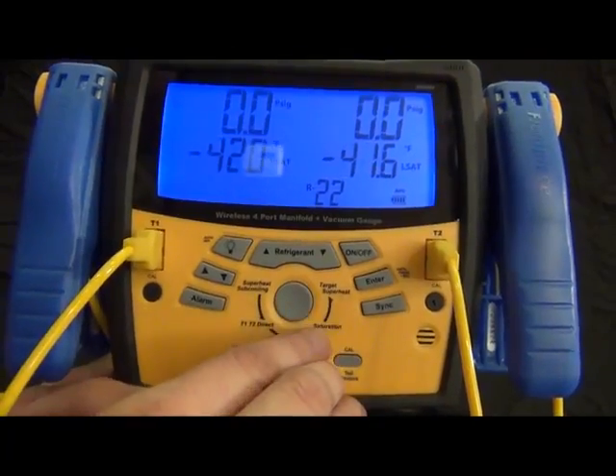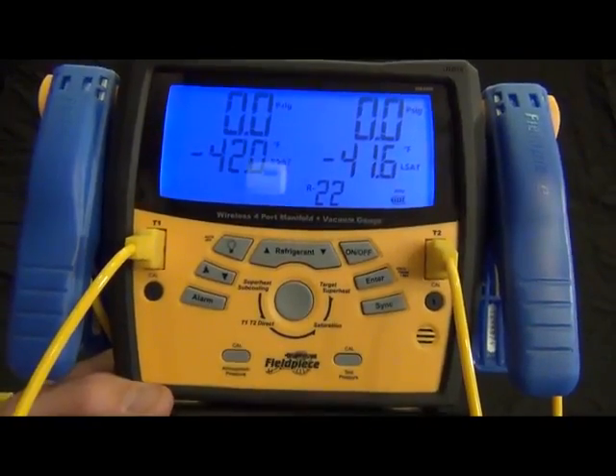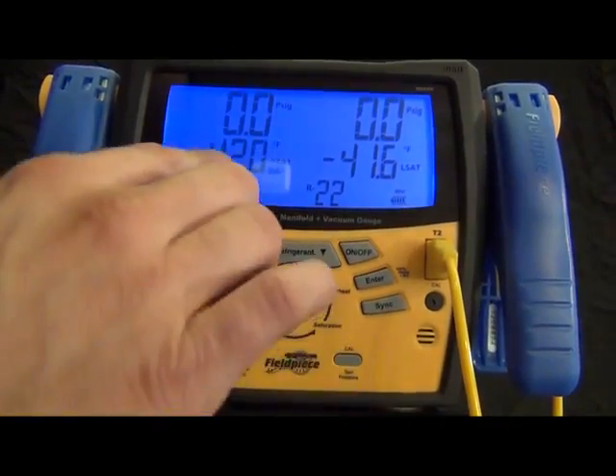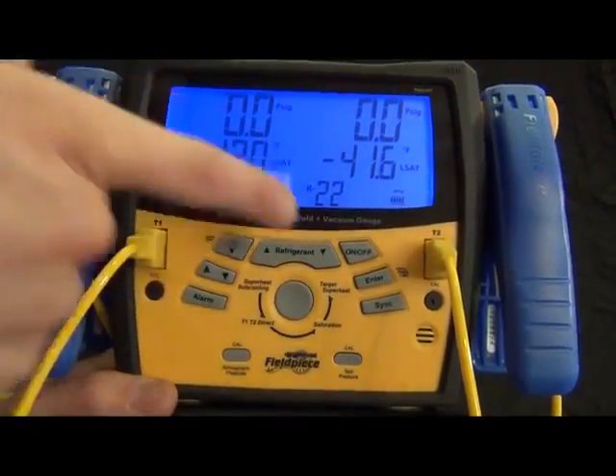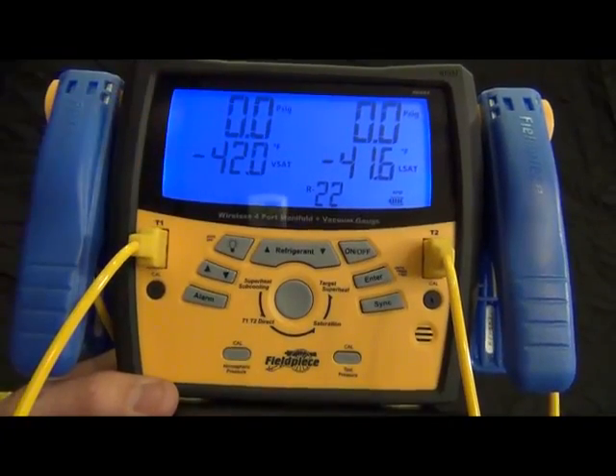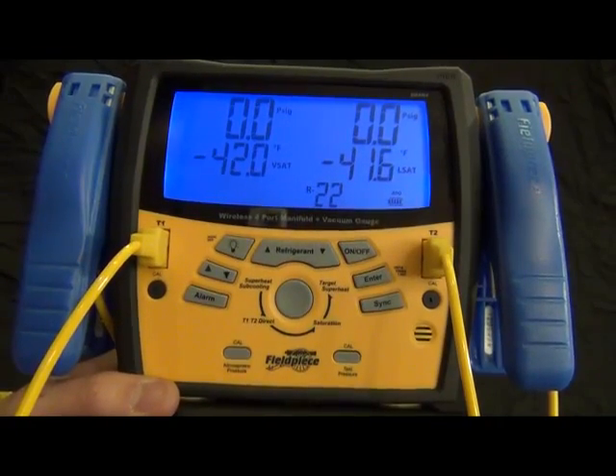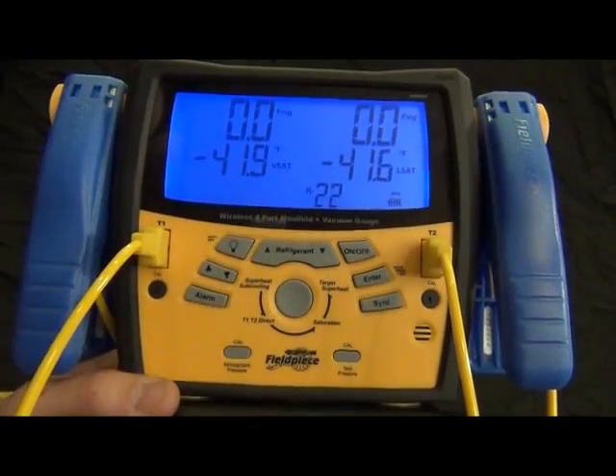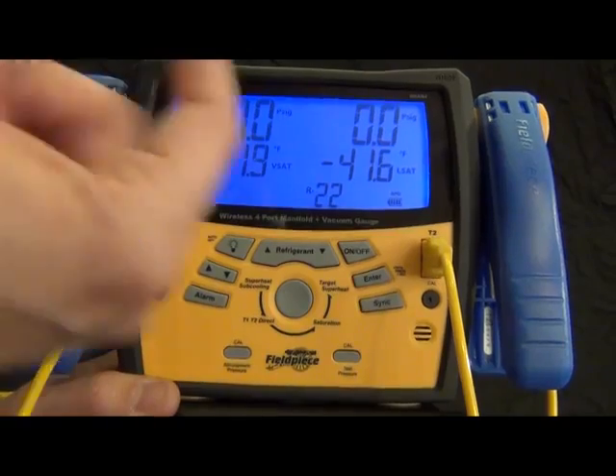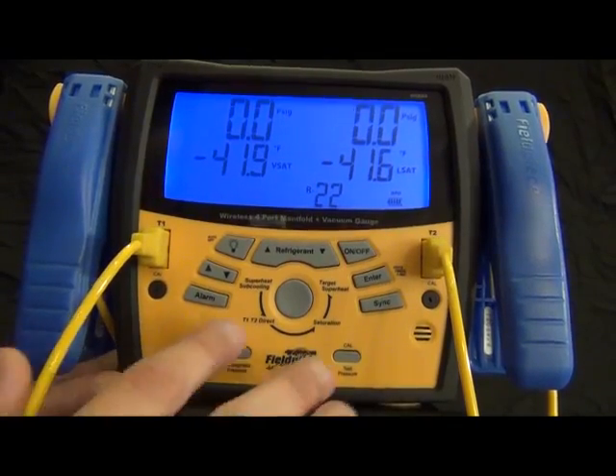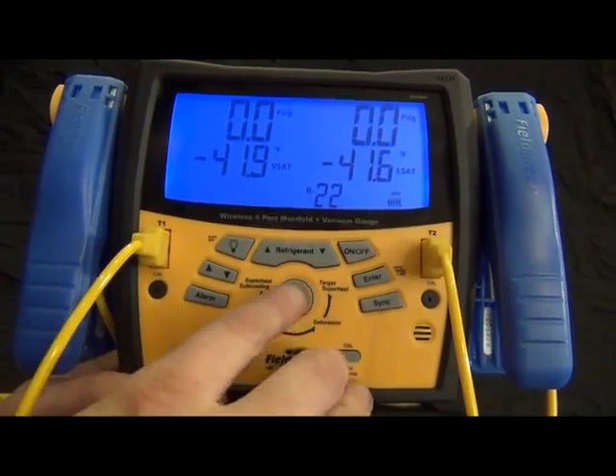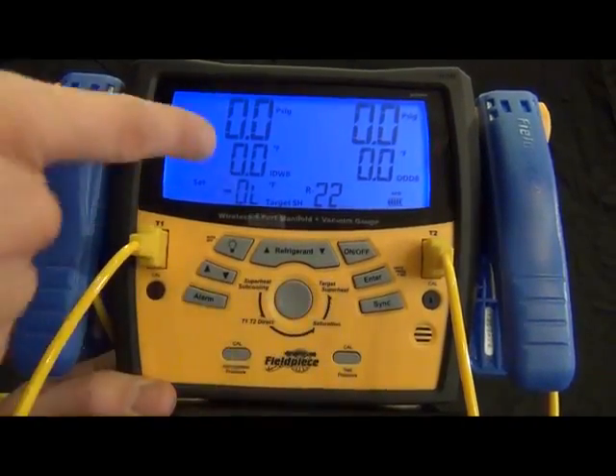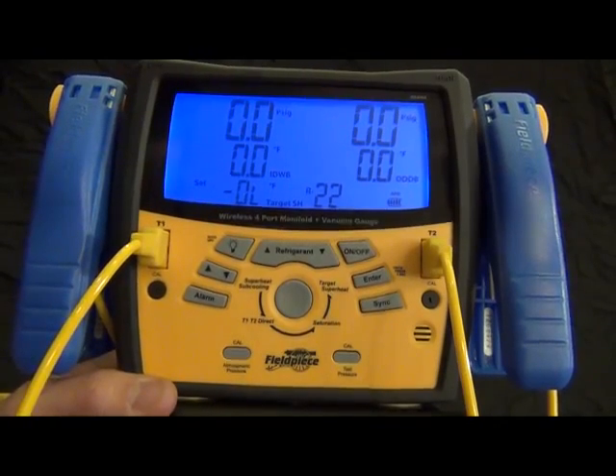All right, next mode is saturation. This is basically your PT chart built right in. And so R22 at zero psi has a vapor saturation of negative 42 and a liquid saturation of 41.6. So very tiny amount of temperature glide with R22.